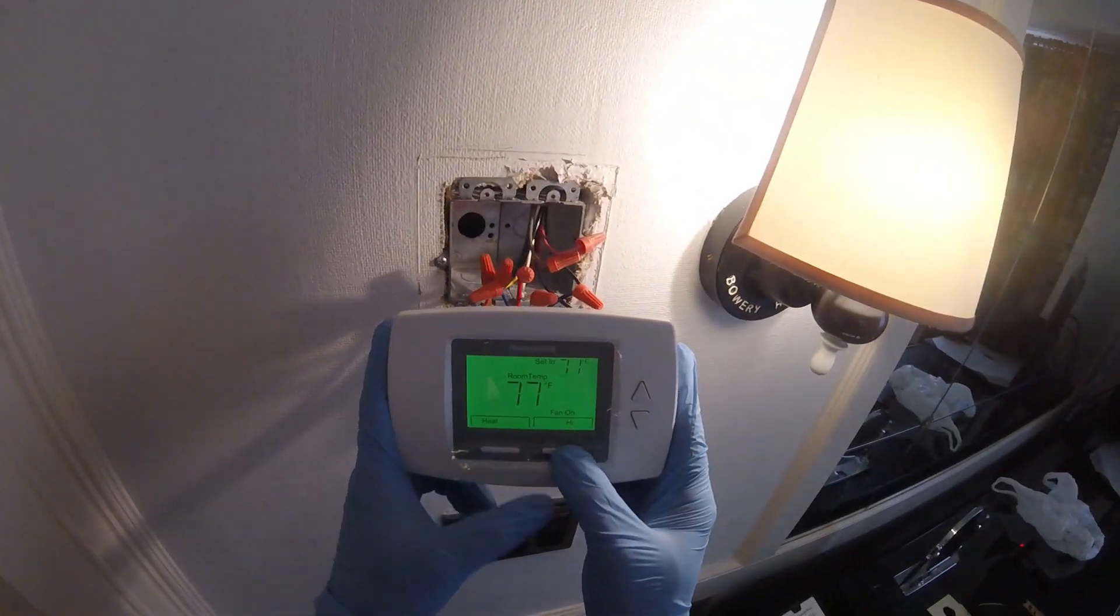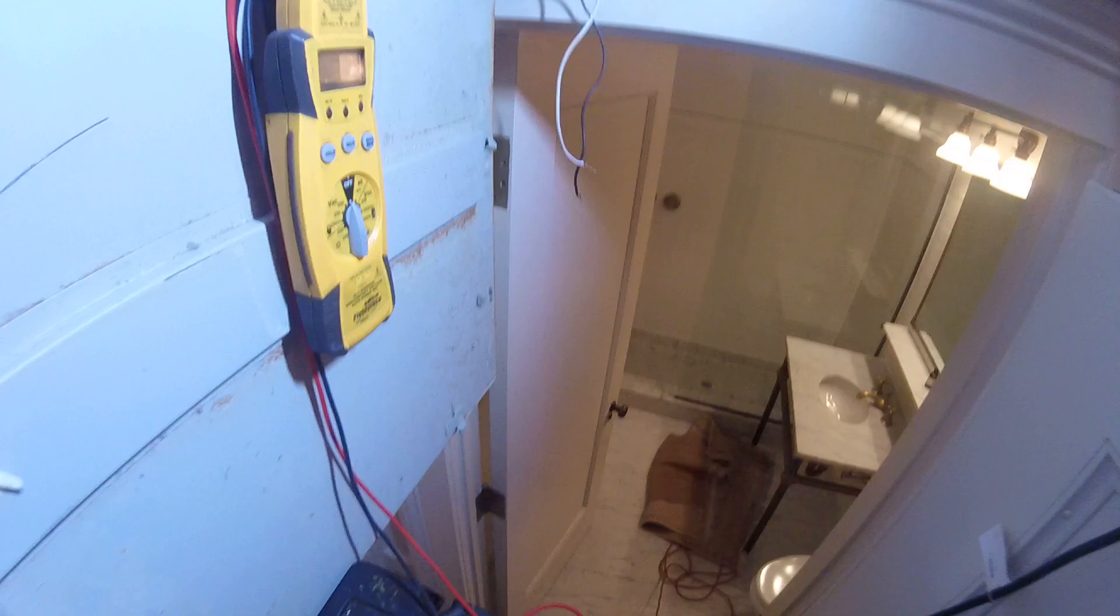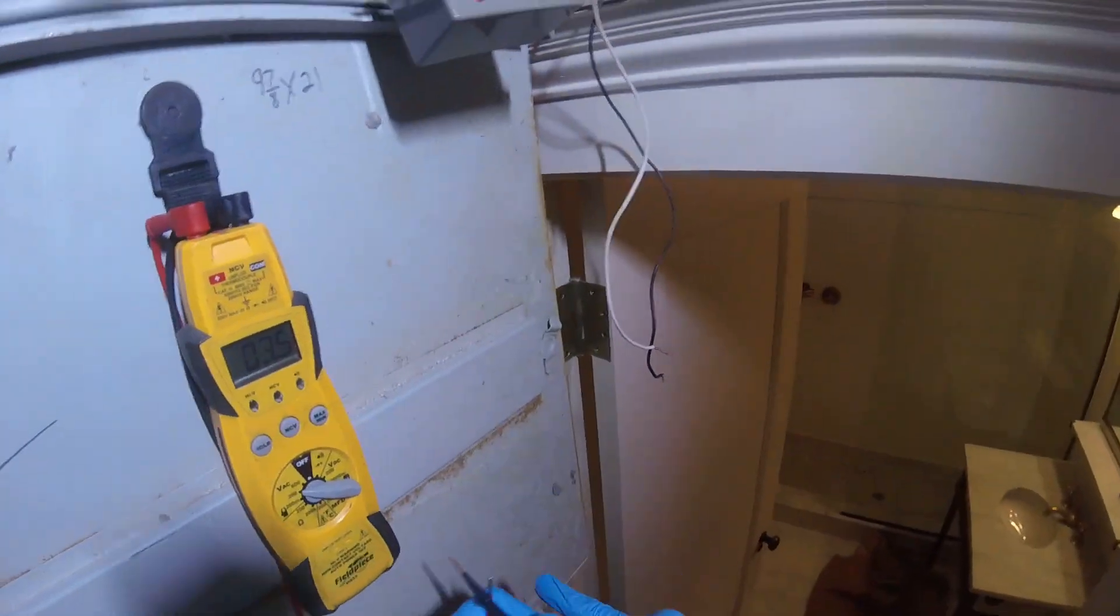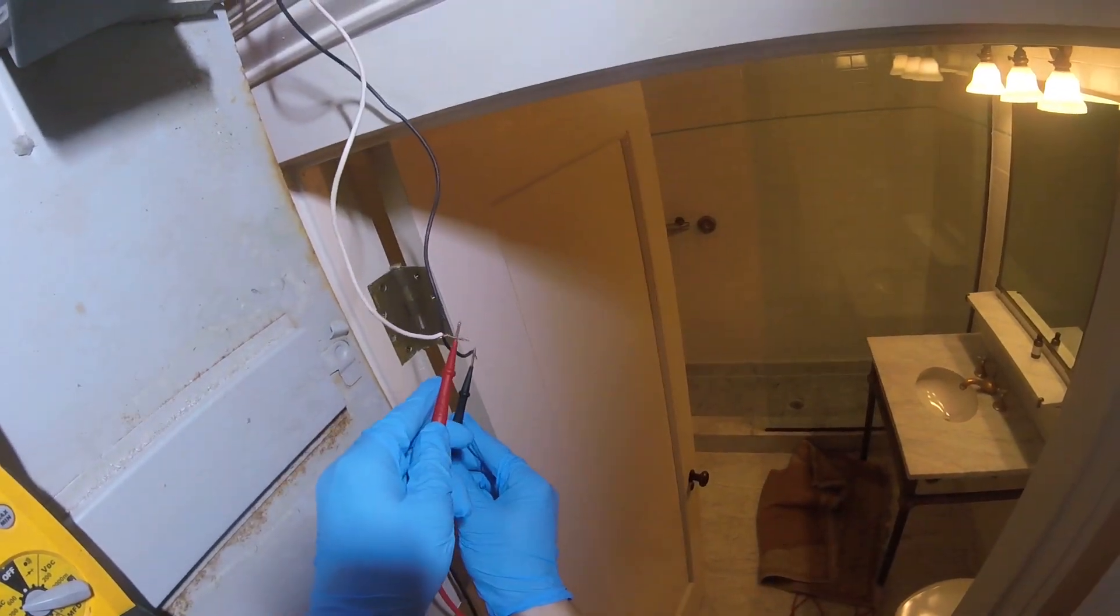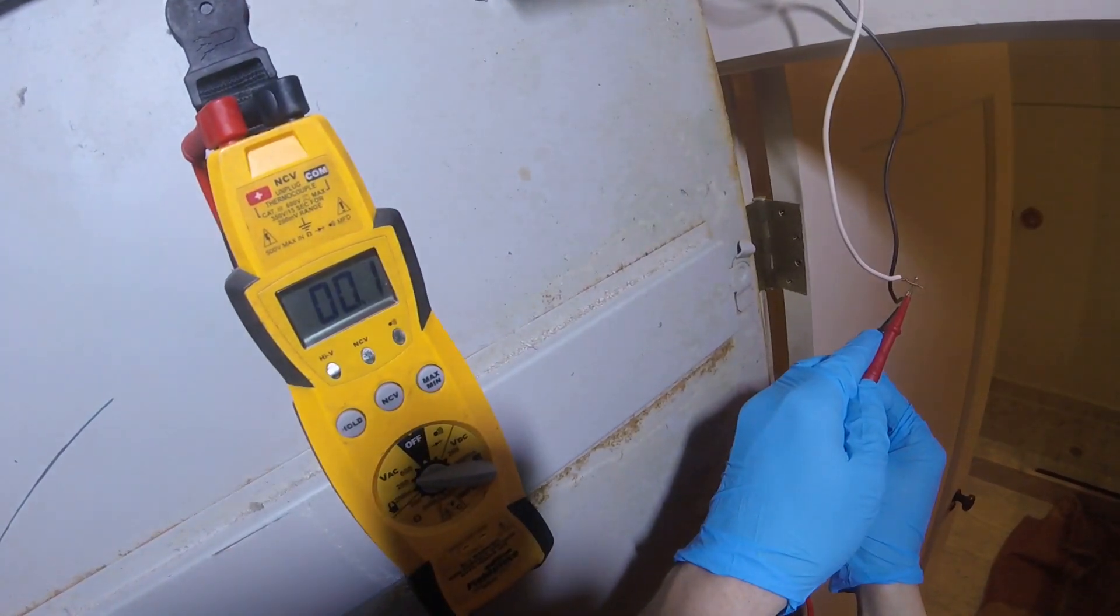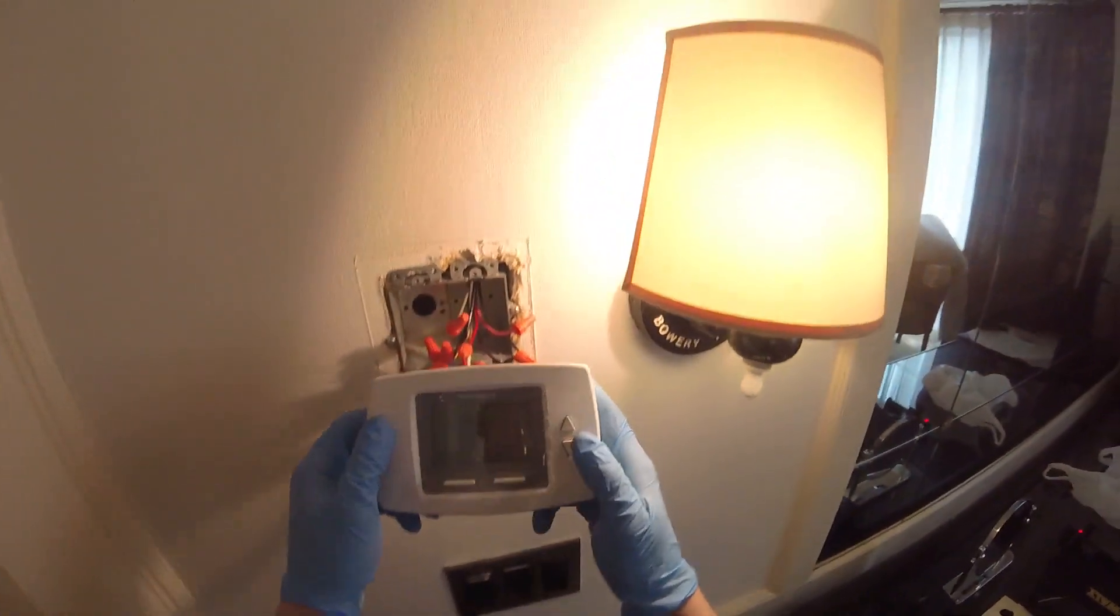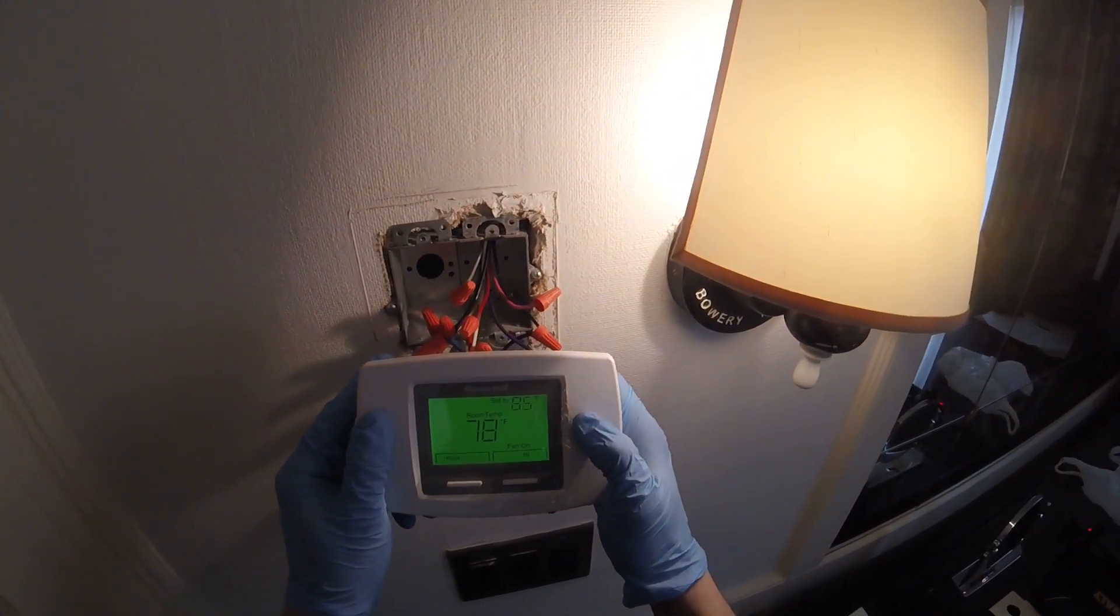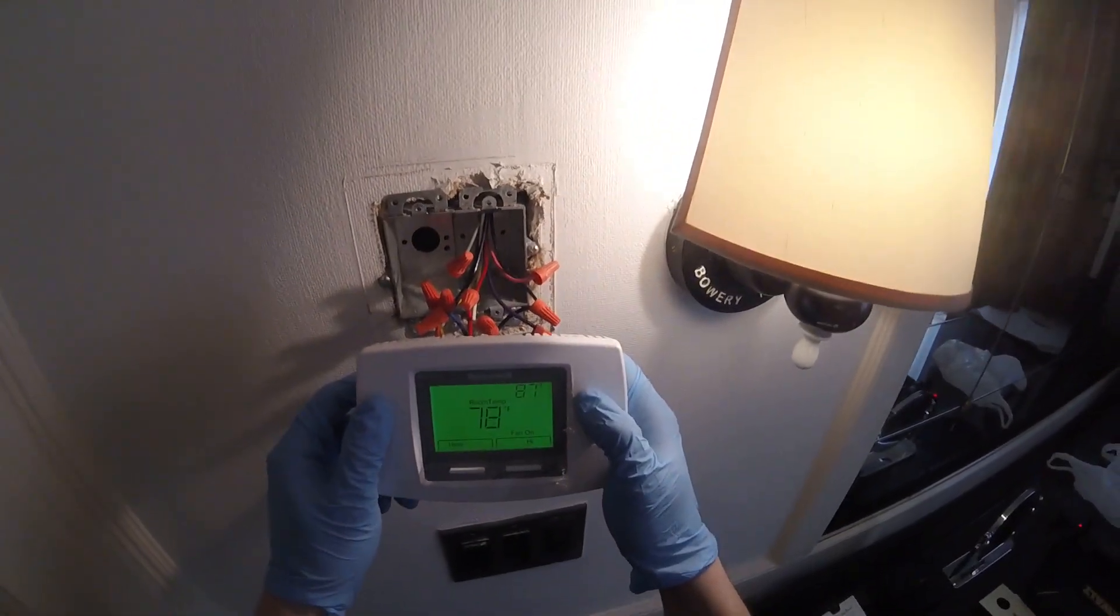Alright, we're set to heat, but our set point is below the room temperature. So let's see. Shouldn't be cooling. So I'm going to check between these two. Nothing. Let's set this thing to heat to see if that valve energizes. So I'm going to raise the set temperature above the room temperature.